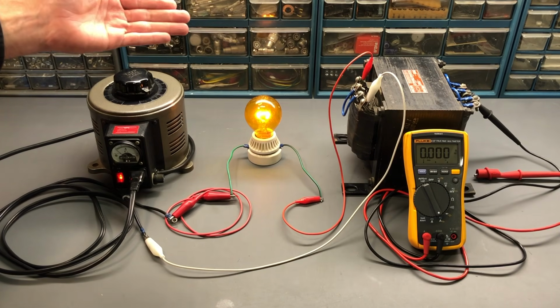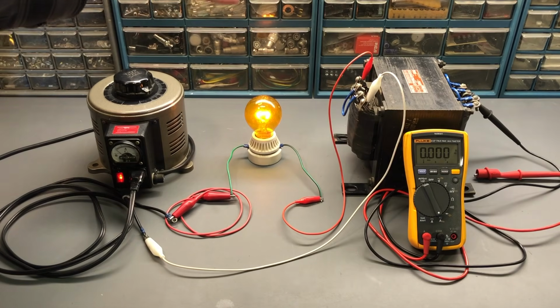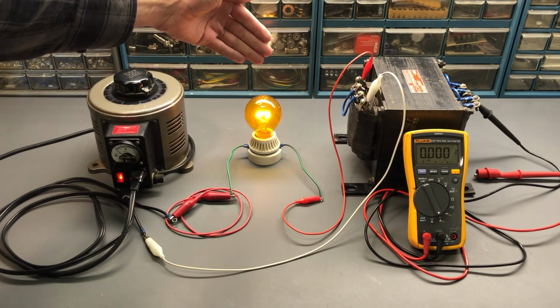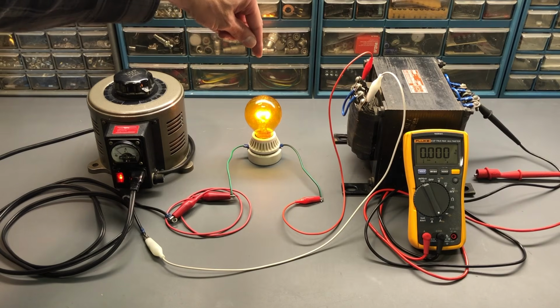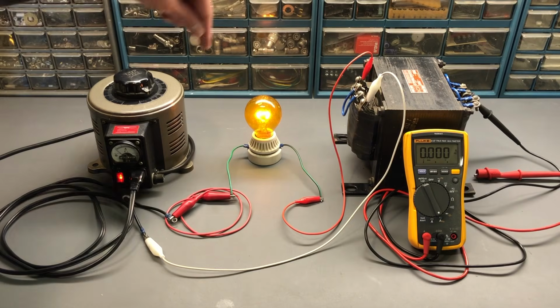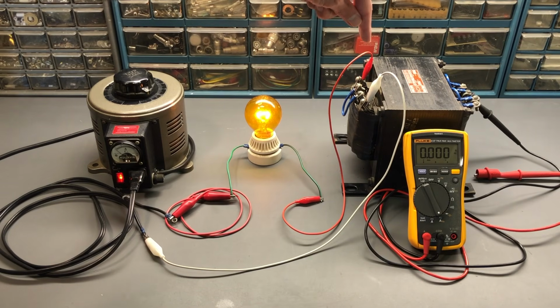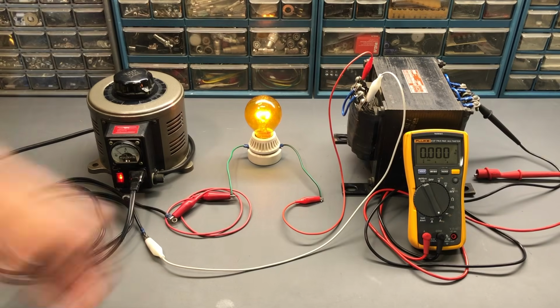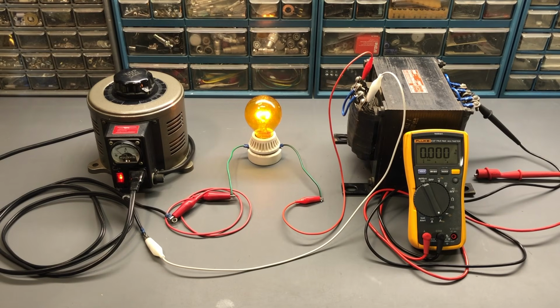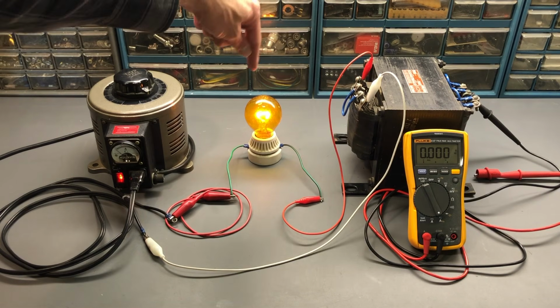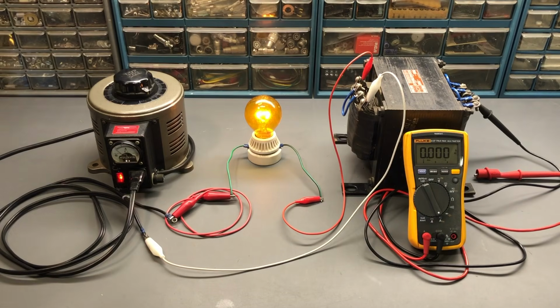So with this configuration, a slight negative effect, or maybe a slight disadvantage, of having the bulb in the middle is that this bulb, particularly with smaller wattage values, will glow all the time. The reason is there's always some current that flows through the primary of the isolation transformer. Transformers aren't a perfect component, and there are losses due to heating, and there's always some current that flows in a transformer winding even with no load on the secondary. That's very obvious with this bulb glowing right now, and there's absolutely no load on the secondary.